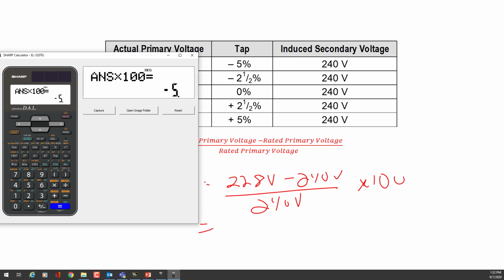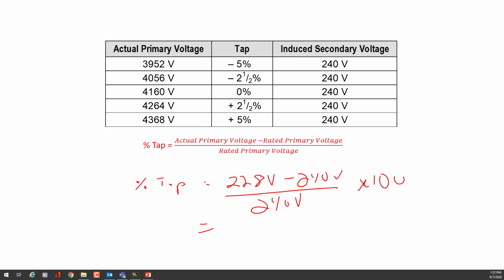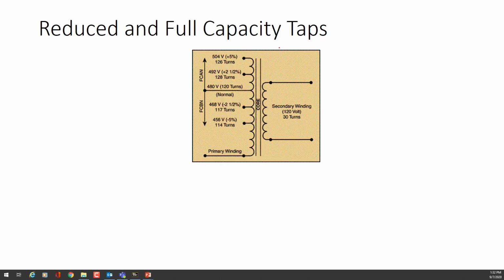Sometimes people look at this and go, oh, shouldn't we add turns in? Like plus, we need to add voltage because of the plus. It's exactly opposite. If we're low on voltage, we have to set it to a negative percent tap. If we're high on voltage, we have to add it to a positive percent tap. So just a little more on this, transformers.